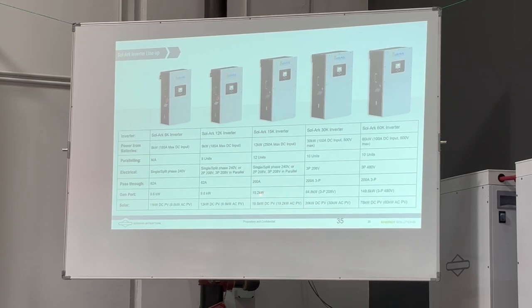You can bring in 19.2 kilowatts through the generator port, so you've got a 100 amp breaker there. And then the solar, you can bring 19.5 kilowatts of DC solar in through 3 independent MPPTs. Okay. Wait, so let's say on the generators also for AC coupling, one of the advantages is it's very easy for retrofit. Somebody that already has a solar array and wants to add batteries, you can use AC coupling and add batteries to the existing solar system.